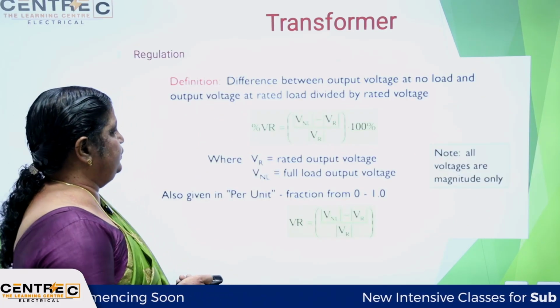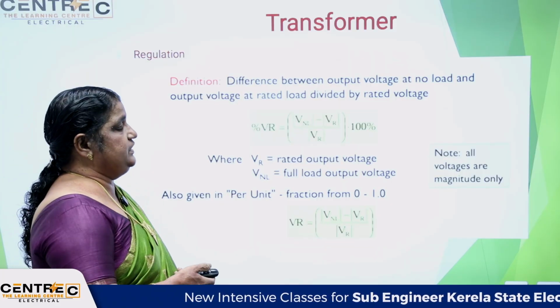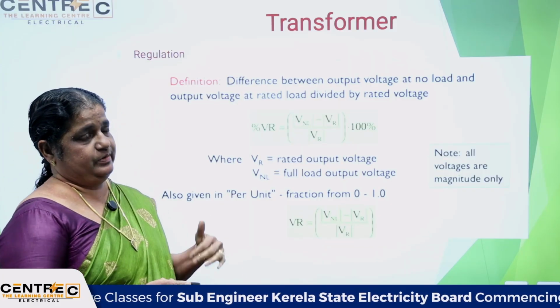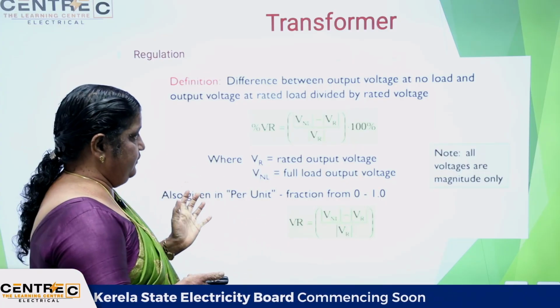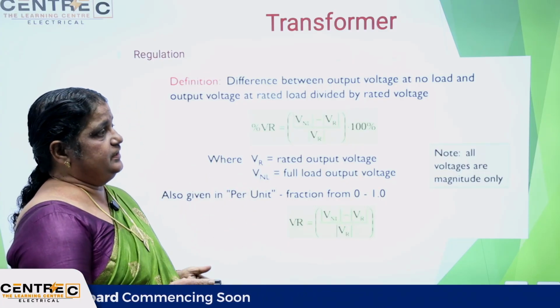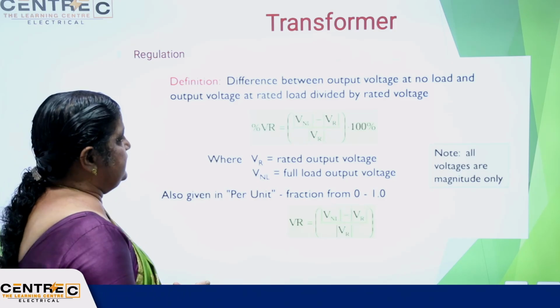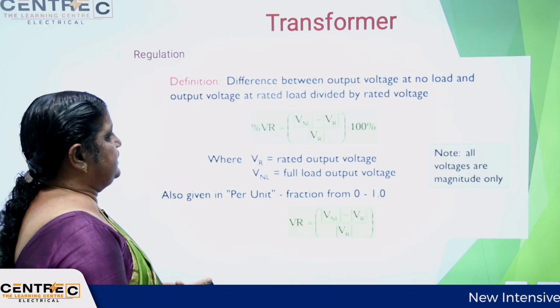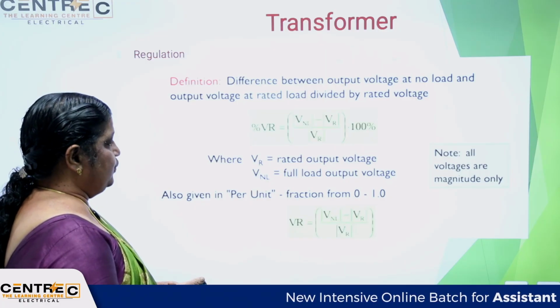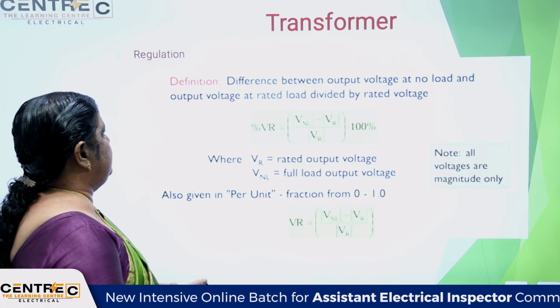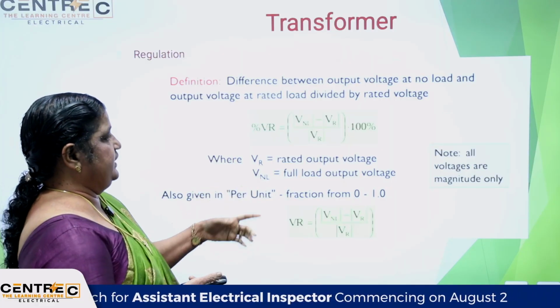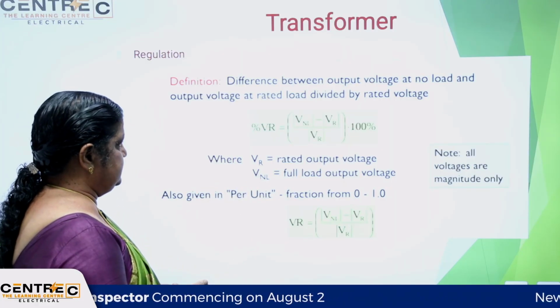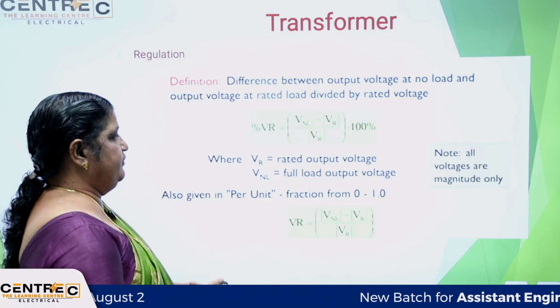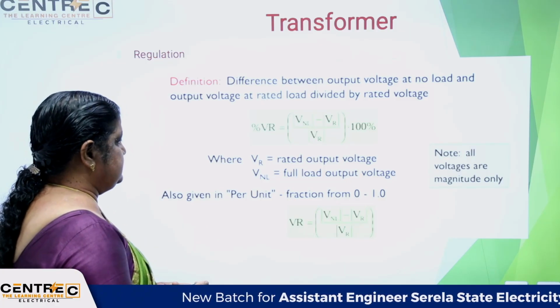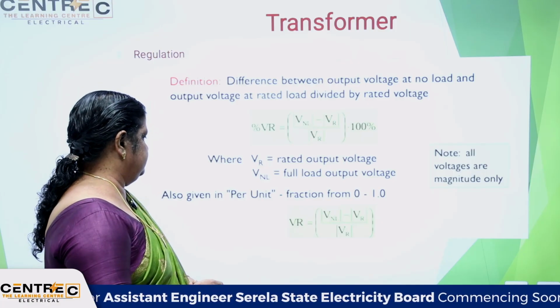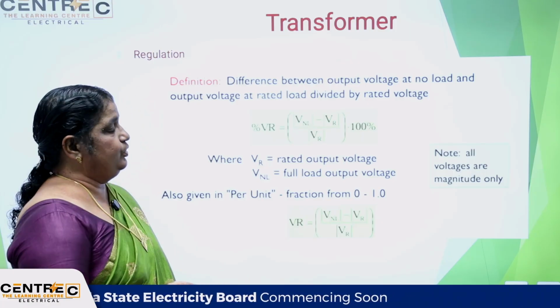Then next we go to the regulation of the transformer. Regulation means that when the transformer transfers a voltage from one voltage to another under no load condition, there is a voltage transfer. Then when the transformer is loaded, the output voltage is reduced. That reduction is the voltage regulation of the transformer. It is VNL minus VR, where VR is the loaded voltage, divided by VR into 100. That is the percentage regulation. Its per unit value is 0 to 1.